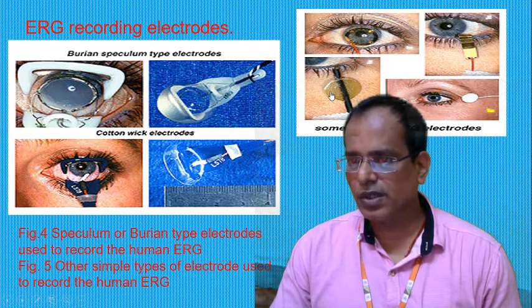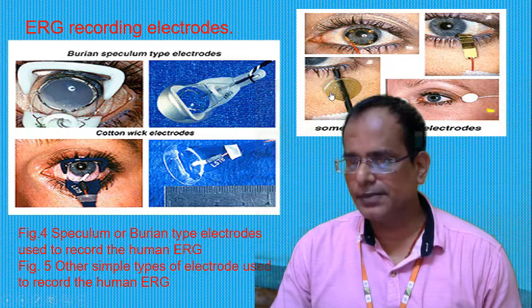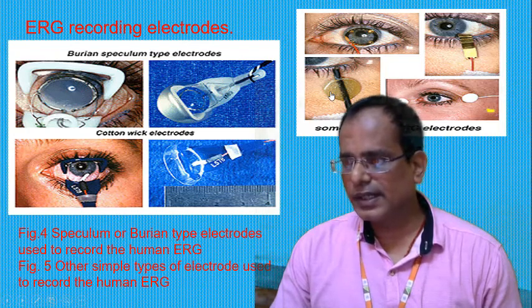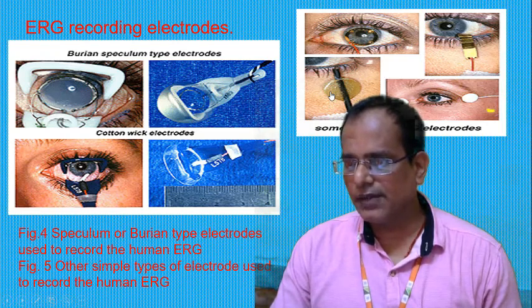Most electrodes are monopolar, that is, they are referred to another electrode site, most commonly on the forehead. Some are bipolar, with the reference electrode built into the metal surface of the speculum. Each of these electrodes records a large voltage response directly from the cornea or sclera, and each has advantages and disadvantages.